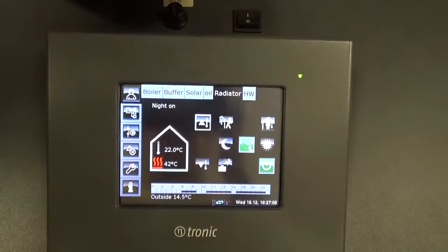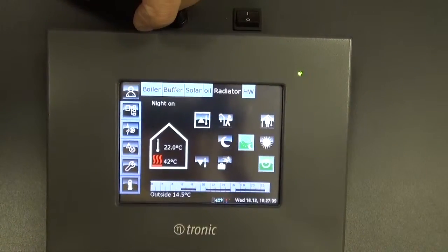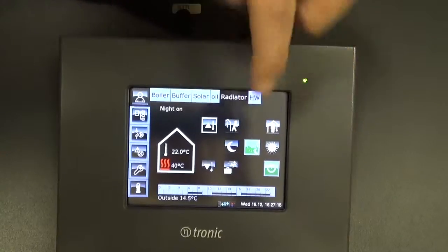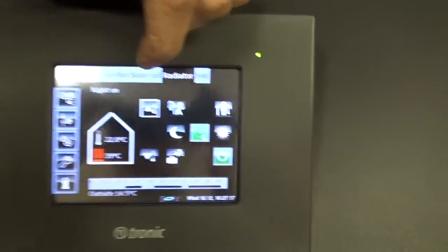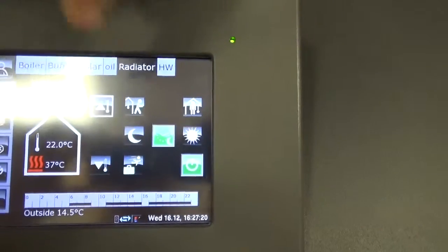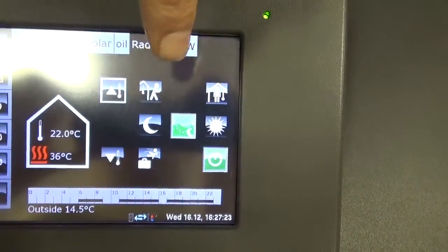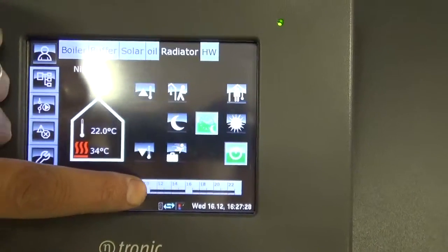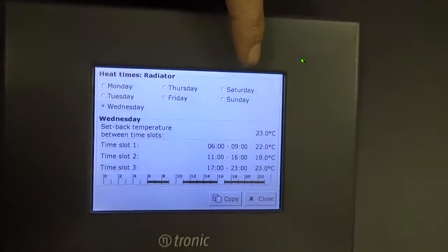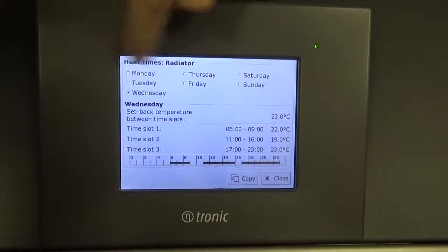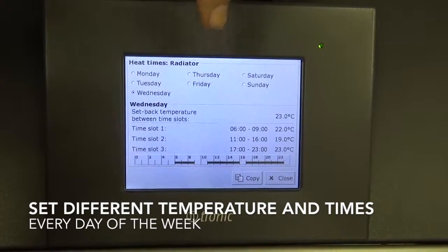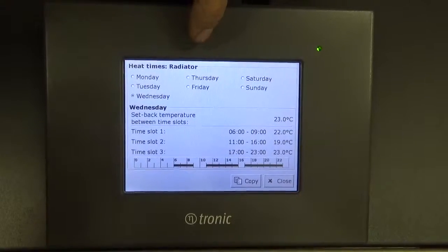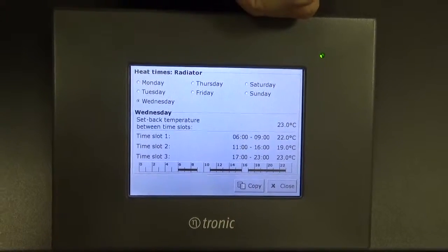You'll notice that the heating has come on to warm the property up. There's also a timer function on the boiler. You'll notice the clock in green, which means the timer function has been activated. To set the time slots for the heating to come on and off, we just click on the time bar at the bottom of the screen. From this screen we have a seven-day timer, so we can set different slots for temperature and time for every day of the week — three different slots for each day — or we can set them all to the same time slots if we wish.